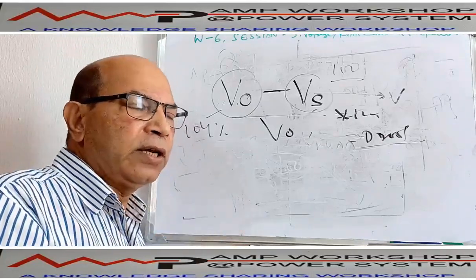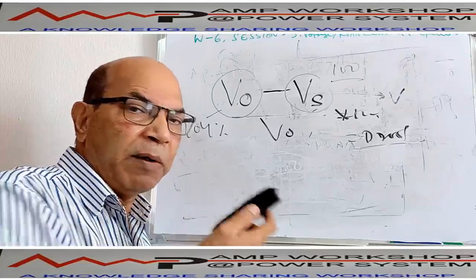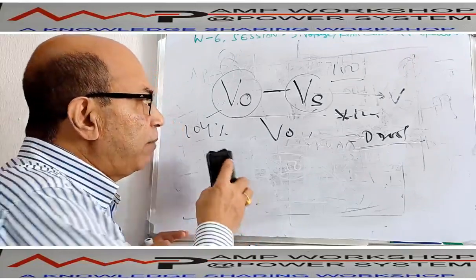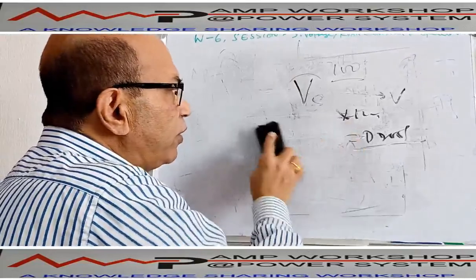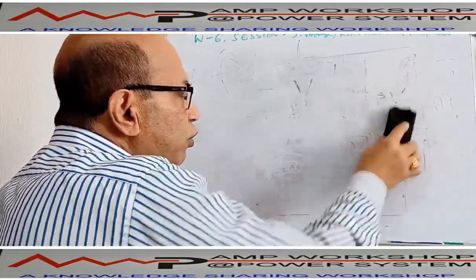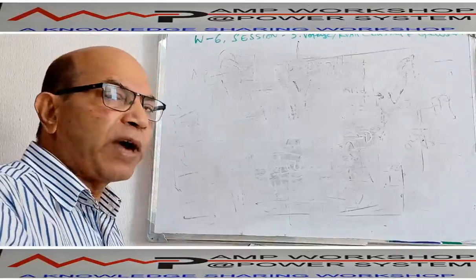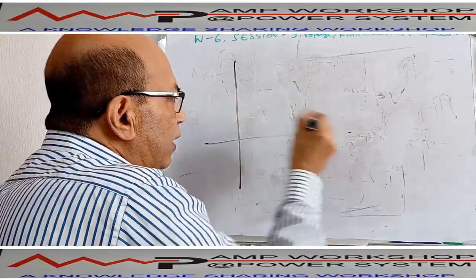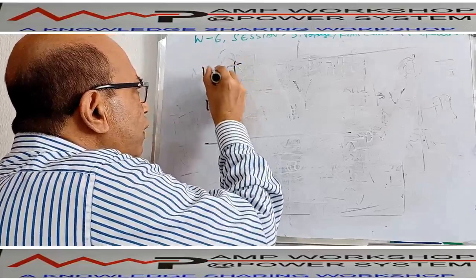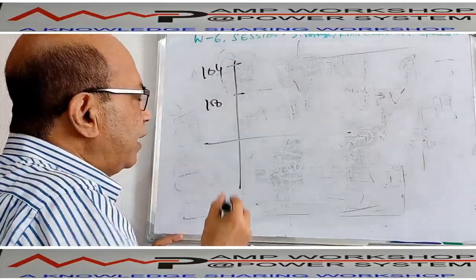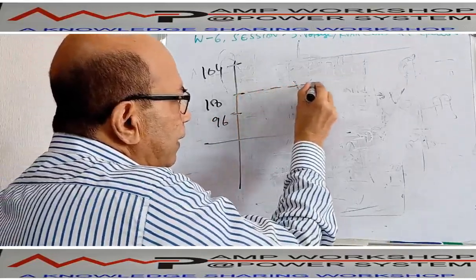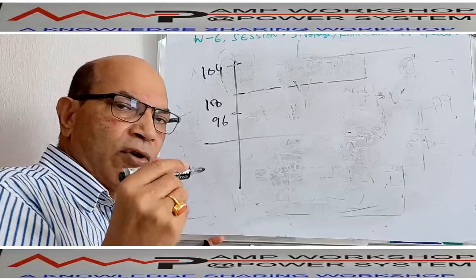We will load the machine based on the capability of the machine. But it is always recommended that the droop setting of all the machines should be identical. Now, if you see the droop characteristic of a machine, it is the same as the active power characteristic. Suppose this is your 100% voltage. If the machine has a 4% droop, then this is 104%, and 96% is the minus side. So this is the 100% characteristic. Now, when the machine is not loaded with kVAr at all, the voltage will be 104%.